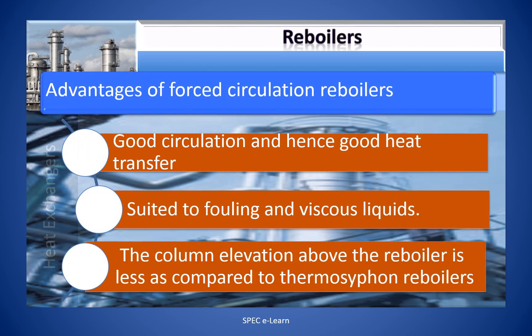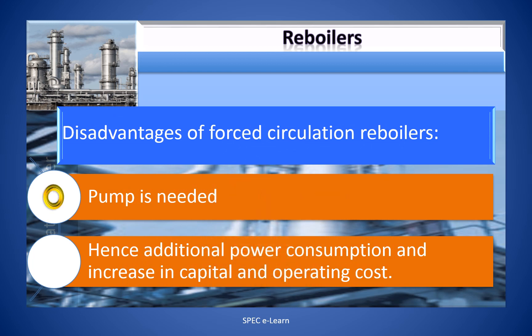The advantages of forced circulation reboilers are: 1. Good circulation and hence good heat transfer. 2. It is suited to fouling liquids. 3. The column elevation above the reboiler is less compared to the thermosyphon reboiler. The disadvantages are: 1. A pump is needed. 2. Additional power consumption and an increase in capital and operating cost.